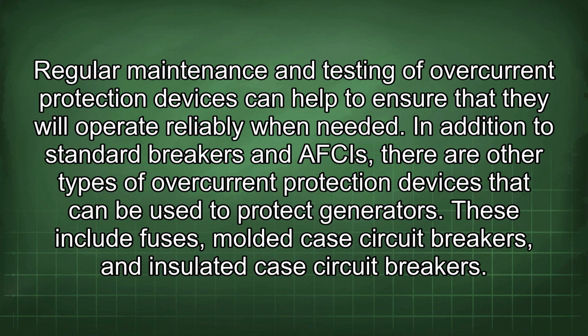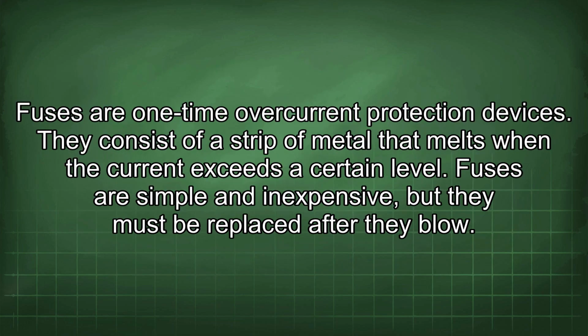In addition to standard breakers and AFCIs, there are other types of overcurrent protection devices that can be used to protect generators. These include fuses, molded case circuit breakers, and insulated case circuit breakers. Fuses are one-time overcurrent protection devices. They consist of a strip of metal that melts when the current exceeds a certain level. Fuses are simple and inexpensive, but they must be replaced after they blow.